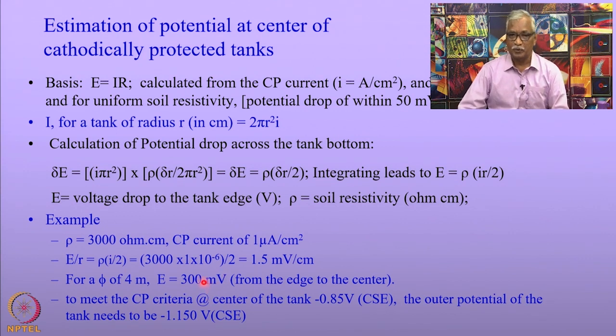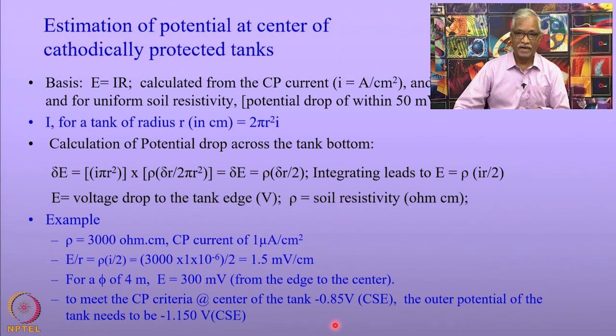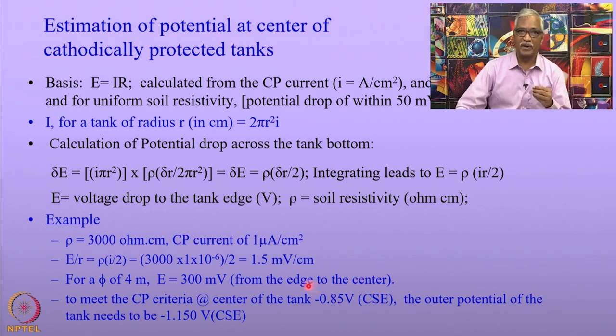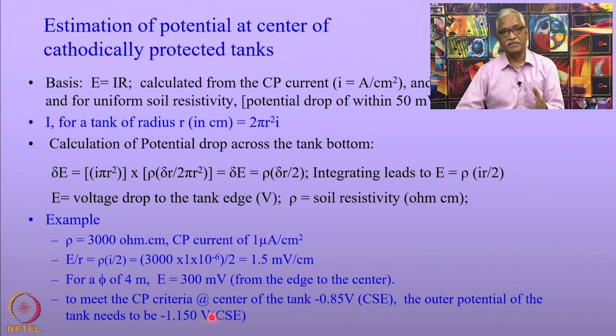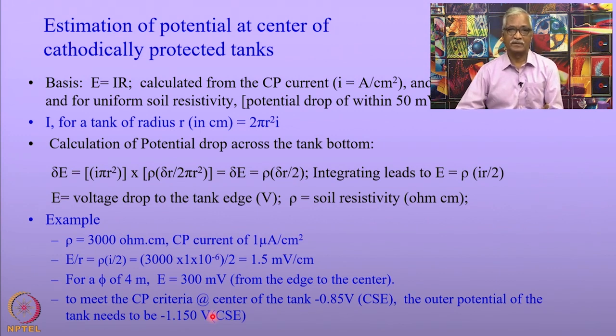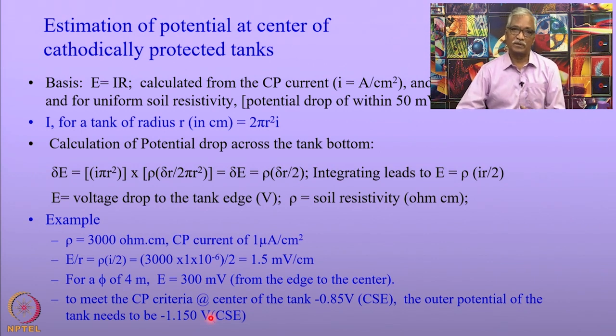Let us look at the criteria for cathodic protection. We know the minimum potential required is minus 0.85 volt with respect to the copper-copper sulfate electrode. Then, if you have to have a potential of minus 0.85 V at the center, the edge of the tank should measure a potential of minus 1.1 volt with respect to the saturated copper-copper sulfate electrode. So it is possible to calculate the potential at the center if we know the soil resistivity and the current density required for cathodic protection.